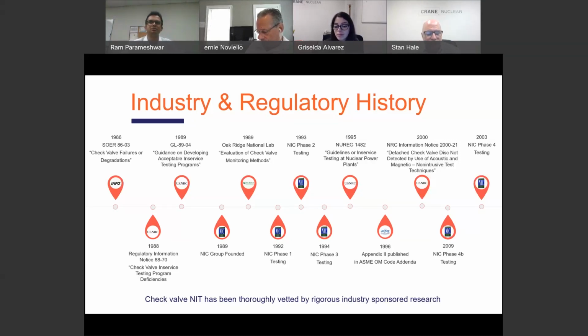I first tested check valves with what we called Checkmate at that time in 1988 at Utah State as part of a utility-sponsored initiative that was led by San Onofre. They had some fairly significant check valve issues back at that time, and I believe they're referenced in 86-03. There were a number of plants that participated, and our objective at that time was to identify promising technologies for check valve testing.